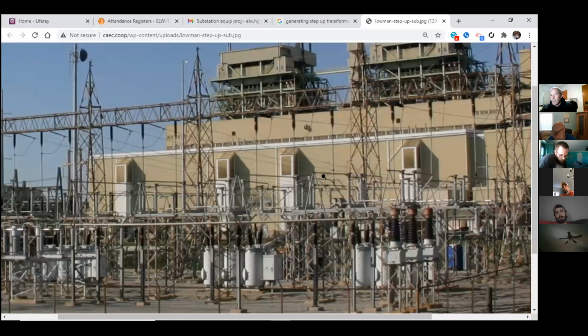But if I'm generating at 34.5 and then outputting on a transmission line, let's say at 230, the rule still applies: if I raise my voltage, I lower my amperage. Vice versa, if I lower my voltage, I raise the amps. So the amperage output from a generating station to the step-up transformer is huge - when I say huge, you're talking 4,000, 5,000, 6,000 amps per phase.